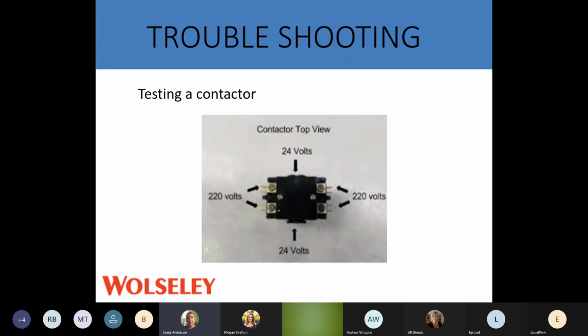And if you throw a screwdriver on there, chances are you're going to get a zap, but you do not have the full capacity of the 220 because we're only bringing it off one leg. So be mindful if you're installing or you're teaching one of the guys out there that he knows properly how to check the 220 out there. I do get calls on it every year. Other side of the contactor is our 24 volts from our indoor unit to outdoor unit. That's going to close our contactor to make everything work.